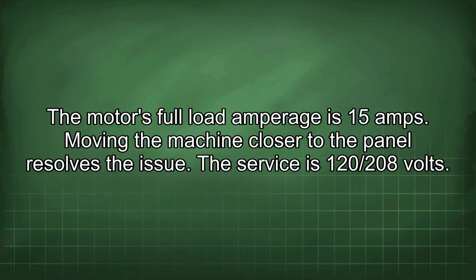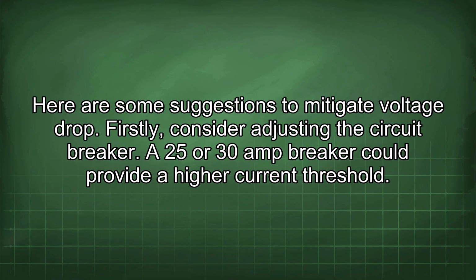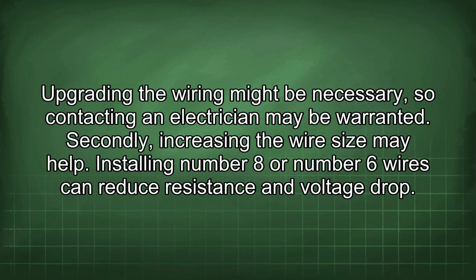The service is 120/208 volts. Here are some suggestions to mitigate voltage drop. Firstly, consider adjusting the circuit breaker. A 25 or 30 amp breaker could provide a higher current threshold. Upgrading the wiring might be necessary, so contacting an electrician may be warranted.